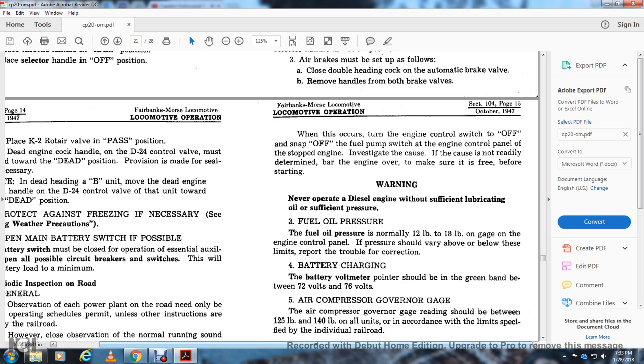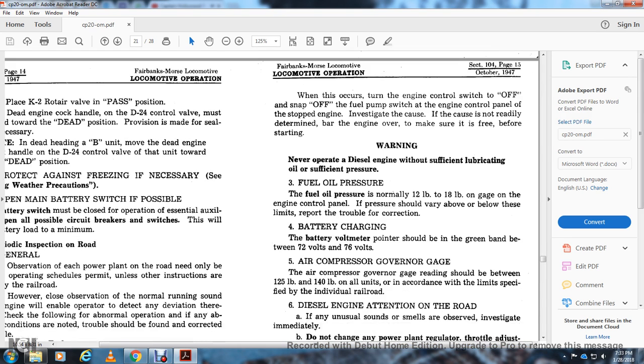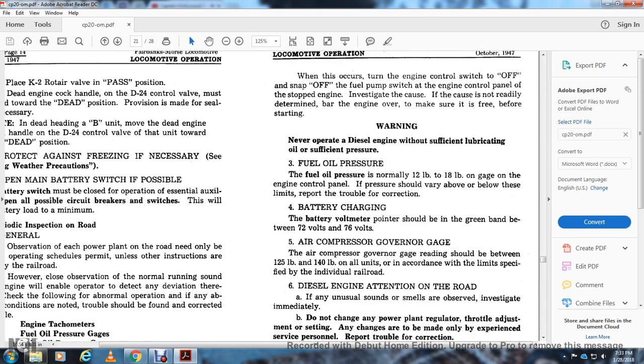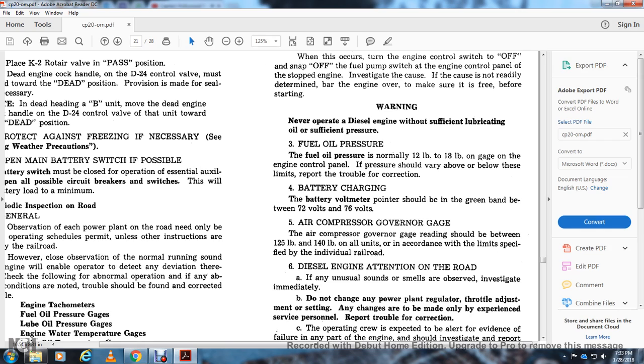Fuel oil pressure is normally 12 to 18 pounds at the gauge on the engine control panel. If the pressure varies above or below the limits, report the trouble for correction. Battery charging: the battery voltmeter pointer should be in the green band between 72 and 76 volts. Air compressor governor gauge: the reading should be between 125 and 140 pounds in all units, according to the limits specified by the individual railroad.